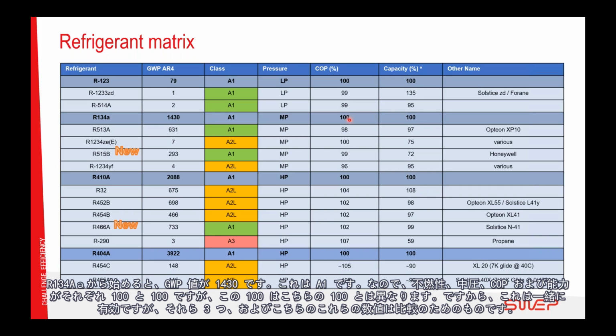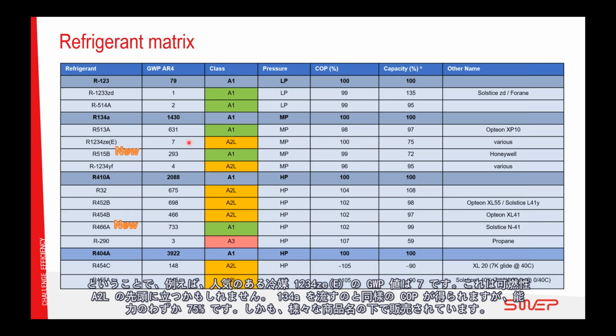And it should be noted that this 100 differs from this 100. So this is valid together, those 3, and then these values here are for comparison. So for example, we can see the popular refrigerant R1234ze(E) has only a GWP of 7. It's mildly flammable, A2L. You get the same COP as with R134A, but only 75% of the capacity. And it's being sold under various names.